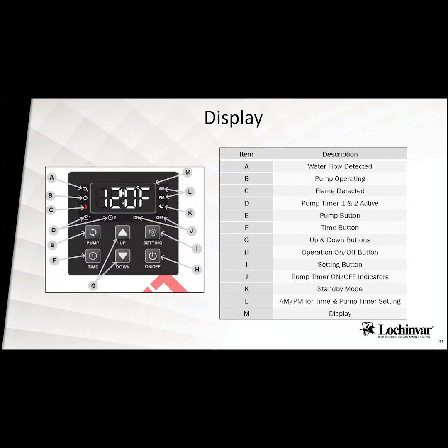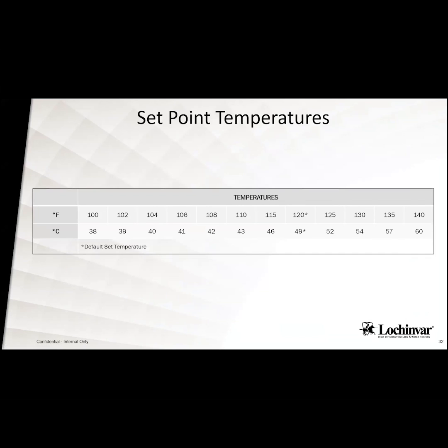All righty. So with the display on here, the typical display built into the front of the unit, it's going to show you when water is flowing through there, when the pump is in operation, when it's burning, the two different pump timers that are built into it, all those different items that you're going to see on that display. These units are going to come set from the factory at 120 degrees. You can turn these up to 140 degrees, but the customer would have to go into the programming to turn that up to 140 degrees. It does come set from the factory at 120. That is there to protect your contractor and also the manufacturer, so that we weren't any higher than that, which can cause scalding.